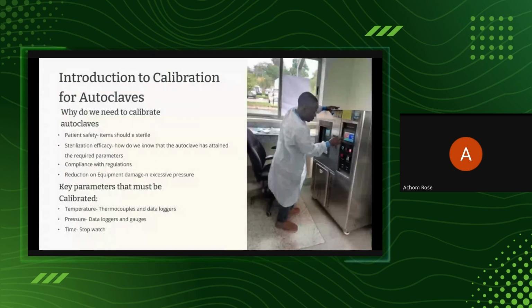Then it also leads to reduction of equipment damage. How or why? When you're doing the calibration, sometimes you may find that this autoclave must be operating at, say, 2 bars. Okay. But then during calibration, you realize that it actually exceeds the 2 bars and goes to even 4 bars. So what will happen eventually? An explosion may occur. Okay. Temperature, maybe it is supposed to be at 134, but in actual sense, it is going up to 150. So you start seeing the boards, the heat sink getting burnt out every time, all that. So it reduces equipment damage. So you reduce definitely the downtime.